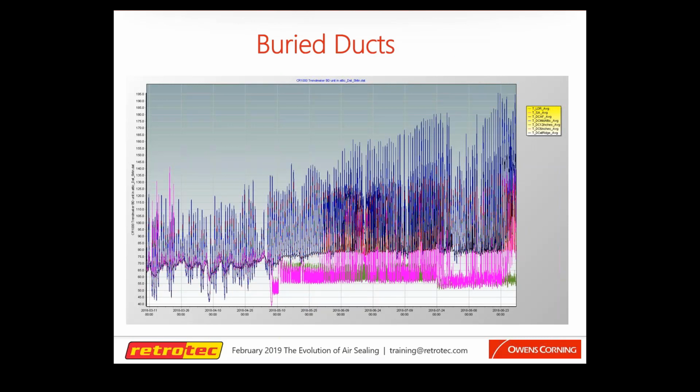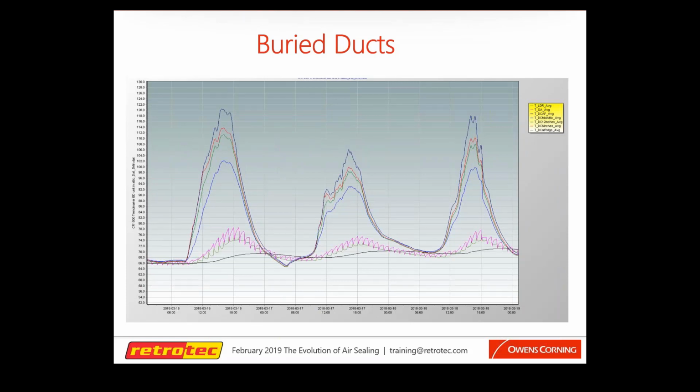What we've been seeing, and I'm not going to get too deep into this, is what you're looking at here: the first line is the level of the roof deck. Your green line is the temperature of the duct and the sensor right above it. What we've been seeing with buried ducts is that on a 120 degree day, when the attic is about 135 degrees, the air coming out of the air handler is at 55, and the air going into the room is at 57.